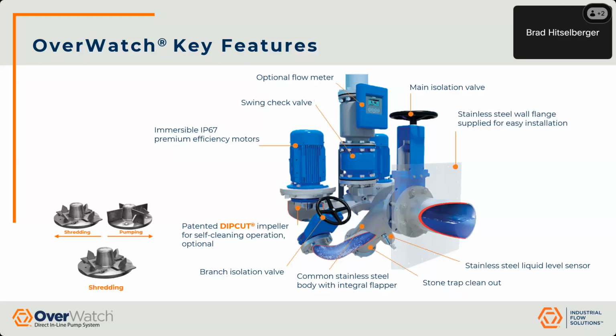So that's sitting right close coupled to the impeller mounting hub, which we'll get into, and it's a recess style impeller. Coming up there is the motors. So the motors are actually immersible. So these are premium efficiency motors. They're IP67 rated. So that's the ingress protection rating. And the 7 of that IP67 means that it will withstand at least 30 minutes of 1 meter of water pressure above the motor. So that is what's guaranteed by the IP rating.